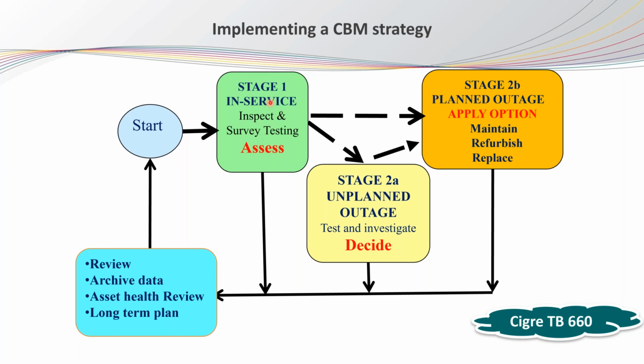And in case there are any abnormalities, any unexpected increasing trend of the measured data, we can go for the forced outage, right? Take the equipment out from the service, do the offline testing to confirm your findings, and then decide the next step, okay, which can be here. Or if everything is fine, everything is good at stage 1, we can follow normally the planned outage for the maintenance directly in stage 2B.